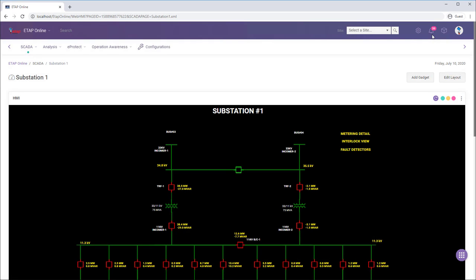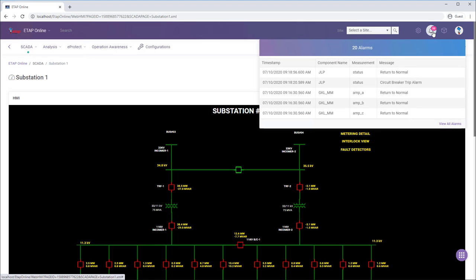This alarm indicator shows the number of unacknowledged alarms we have. The initial list displays the last 5 most recent alarms with details such as timestamp, component name, measurement type, and a message. However, these details can be defined by the user. The alarms displayed are based on an area of responsibility, so you will only see alarms for your specified area. These alarms can also be emailed or texted to the appropriate personnel.